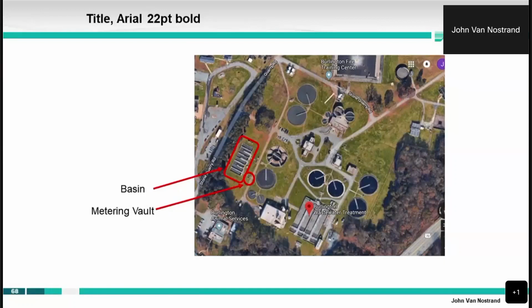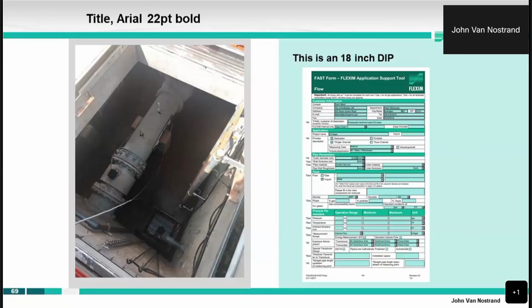So in this particular case, we had East Burlington, North Carolina. They had a basin and a metering vault next to the basin at the wastewater treatment plant, and they have a full bore Magmeter installed down there. This is what it looks like from the top. And you can see, here's the Magmeter. The flow is going from the top of the picture to the bottom, and there are transducers on the pipe.